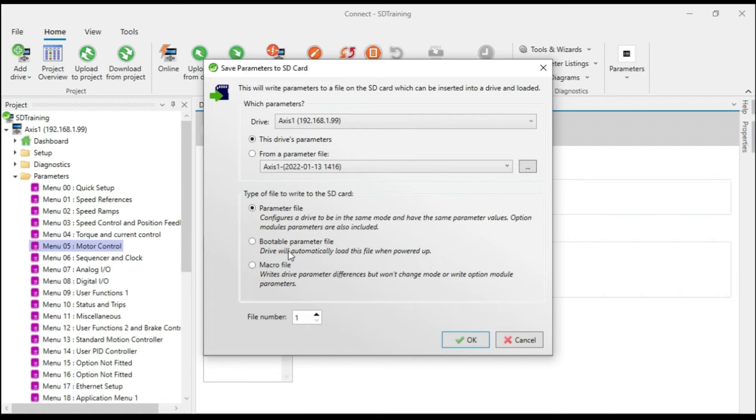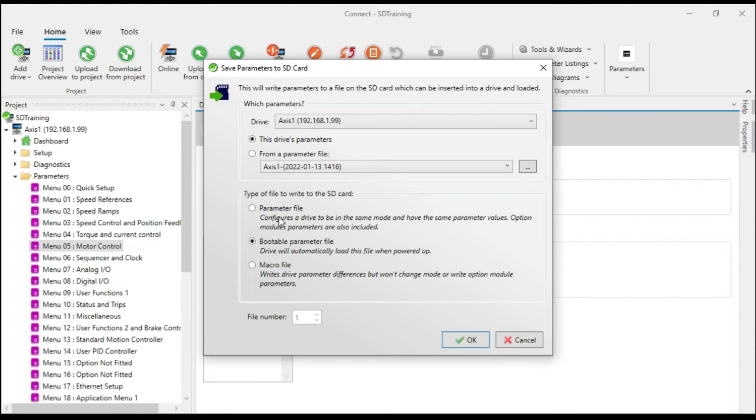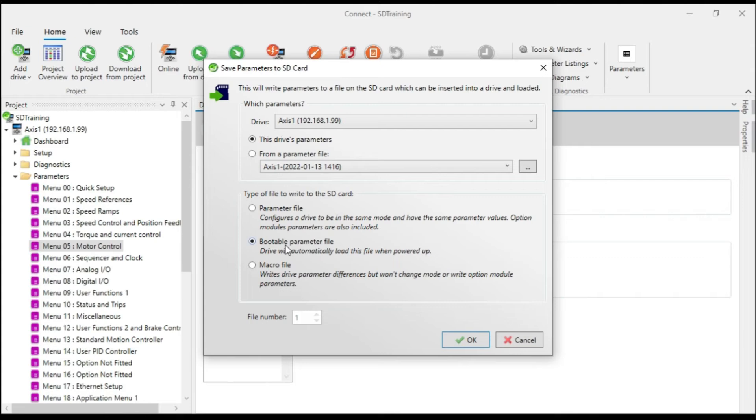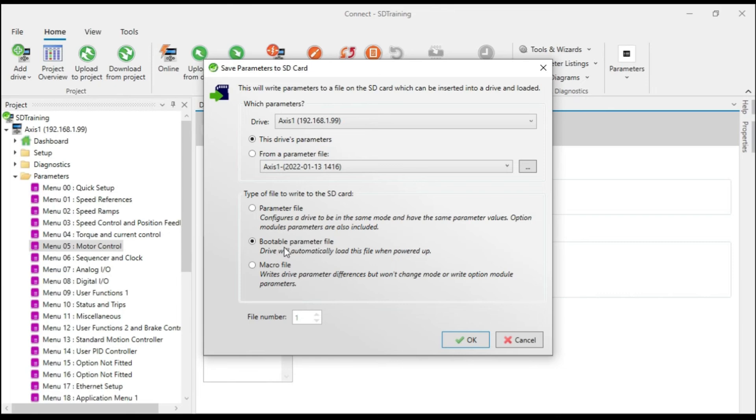The bootable parameter file is quite nice. What a bootable parameter file will do is if I were to tick this, what's going to happen is it's going to write the configuration parameters to the SD card just like it would here, but it's going to set the boot flag on the SD card. And what that means is if this particular drive were to fail, for example, and I replace it with another one, as long as the SD card file is bootable, I would insert this SD card into my replacement drive. And on initial power up, the drive will read the parameters from the SD card into the drive's memory. So you sort of save a step. If it's a bootable parameter file, you don't need to load the parameters from the SD card into your new drive manually.